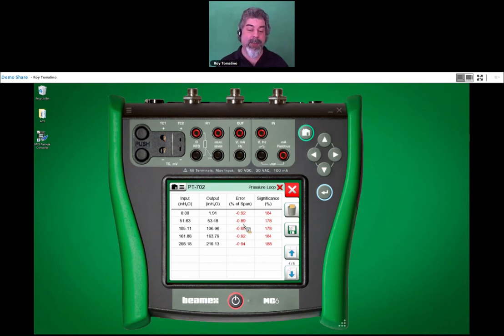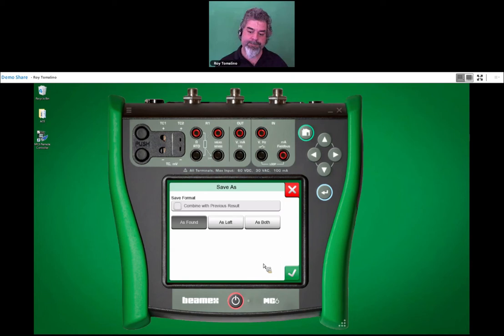So what do I do? Trash can? You're really bad. I'm really bad. Yeah. So you may have a thought to trash can this and to hide all the evidence that you just failed the test, but that's not what we're about. We're about recording your as found as ugly as it is. We'll fix it, and then we'll record an as left. So let me save this. I'll save it as found.